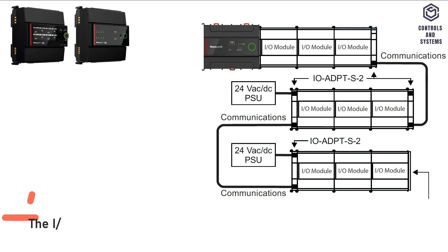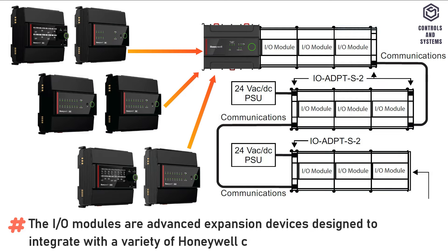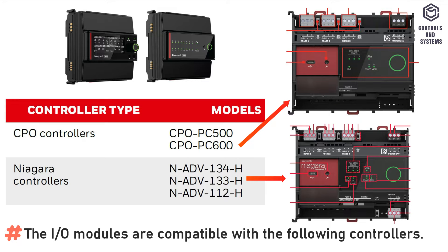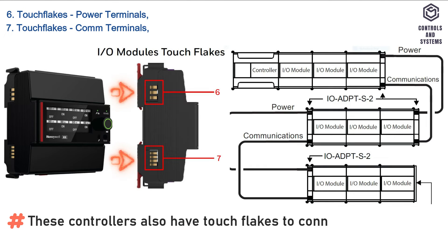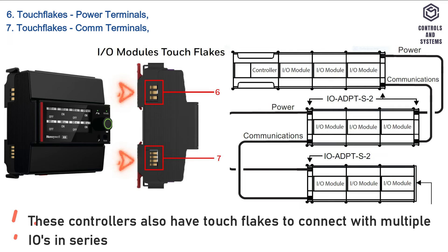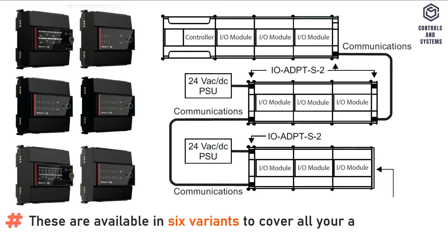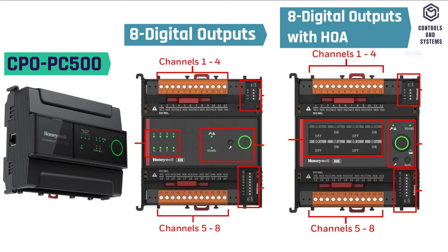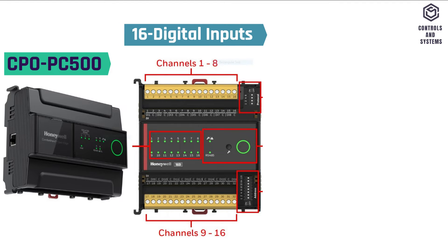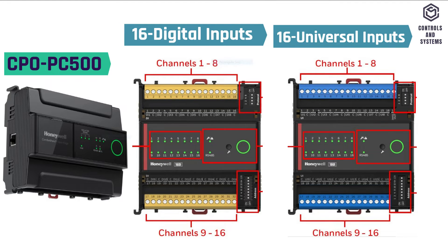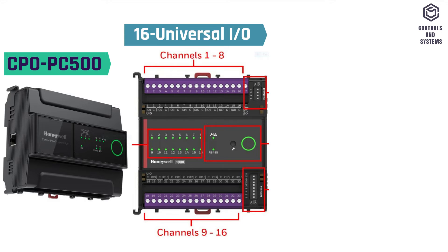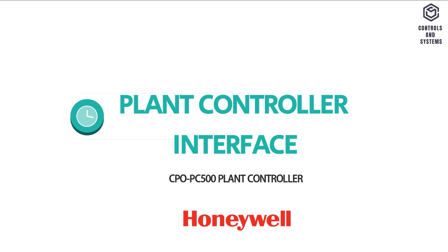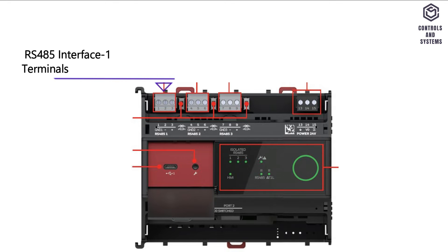I/O Modules: The I/O Modules are advanced expansion devices designed to integrate with Honeywell controllers, compatible with the following controllers. These controllers also have touch flakes to connect with multiple I/Os in series. They are available in 6 variants: 8 Digital Outputs Module, 8 Digital Outputs with HOA Module, 16 Digital Inputs Module, 16 Universal Inputs Module, 16 Universal Input and Output Module, and 16 Universal Input and Output with HOA Module.